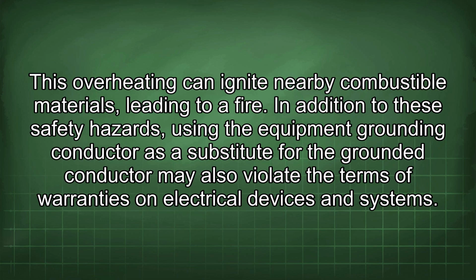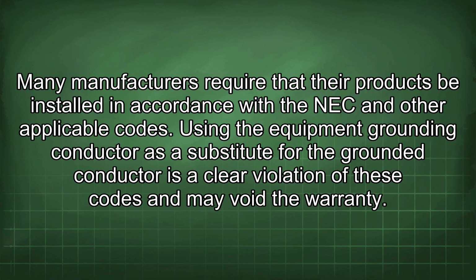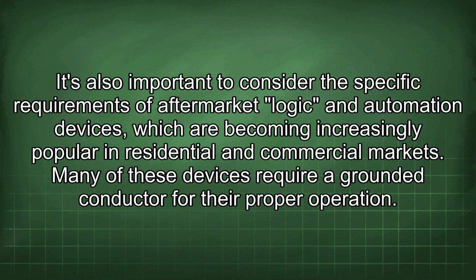In addition to these safety hazards, using the equipment grounding conductor as a substitute for the grounded conductor may also violate the terms of warranties on electrical devices and systems. Many manufacturers require that their products be installed in accordance with the NEC and other applicable codes. Using the equipment grounding conductor as a substitute for the grounded conductor is a clear violation of these codes and may void the warranty.